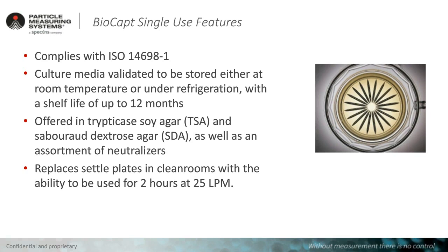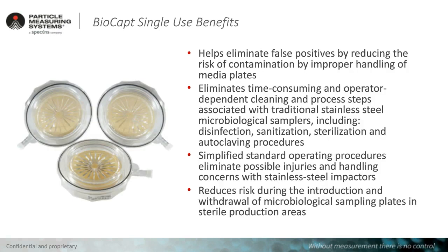Some of the benefits of BioCapt single use: they help to eliminate false positives by reducing the risk of contamination by improper handling of media plates. They also eliminate the time-consuming and operator-dependent cleaning and process steps associated with traditional stainless steel samplers. This includes disinfection, sanitation, sterilization, and autoclaving procedures. This can create a simplified SOP that eliminates possible injuries and handling concerns with stainless steel impactors. It reduces the risk during the introduction and withdrawal of microbiological sampling plates in sterile production areas.